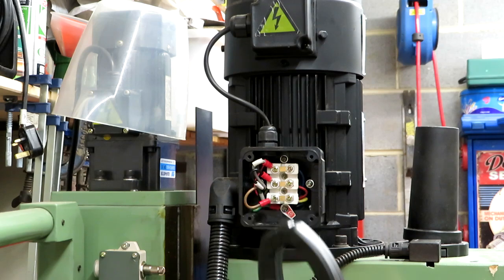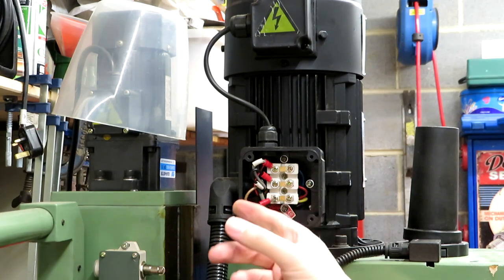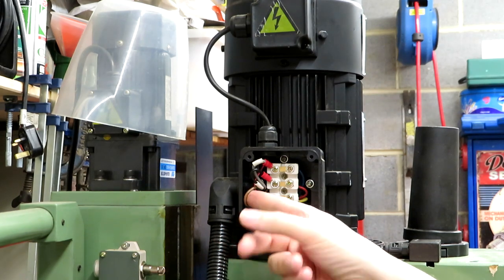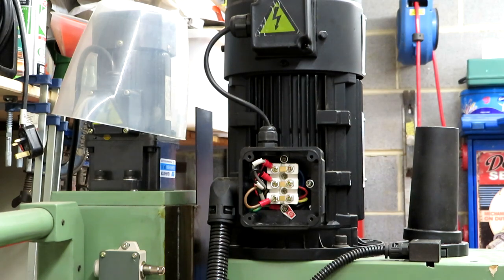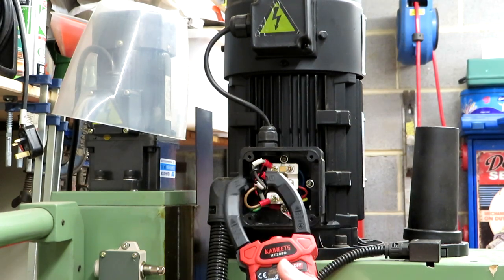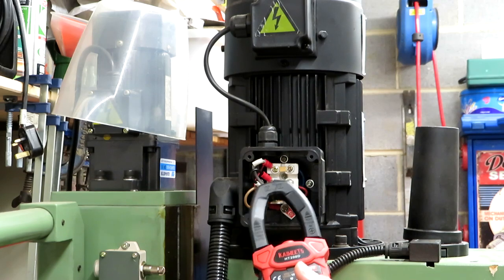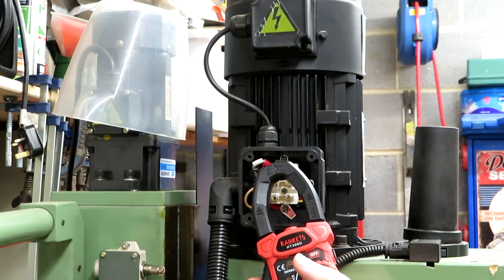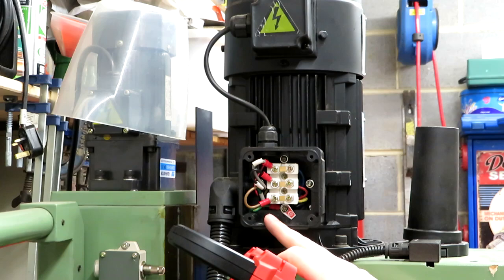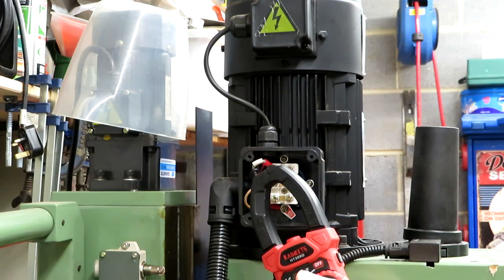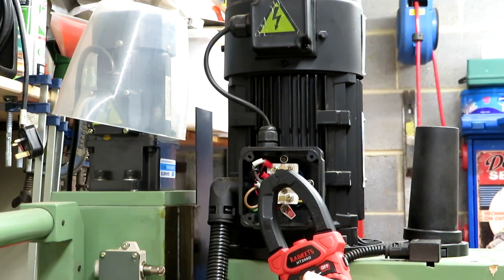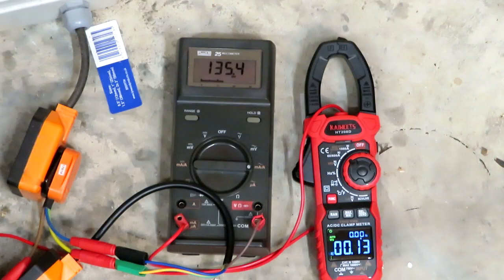But unfortunately in this case we would actually have to disconnect the wiring because there isn't quite enough wire here. The loop of wire that she's given us is just not quite big enough to get the head of the clamp meter onto it, unfortunately. So rather than making the current measurement from the terminal box here, which is what I intended, we will have to make it in the supply cable to the machine. We've got both the Fluke 25 and the KAIWEETS clamp meter installed in the supply line to the milling machine, so let's go ahead and start it up.